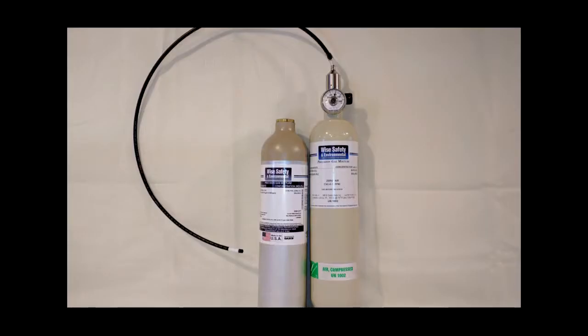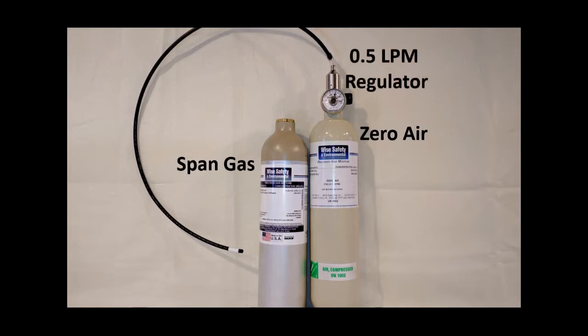When the unit is in calibration mode, the relay outputs of the ECO detector will not activate with gas applied. The 4 to 20 milliamp signal will read 2 milliamps, indicating the detector is in calibration mode. To begin, you'll need a bottle of zero gas, also known as zero air, a bottle of span gas that matches the detector you want to calibrate, a half liter a minute regulator with a 1/4 inch outer diameter tube. Mark the tube at approximately 4 millimeters to prevent overinsertion into the calibration port, which can damage the detector.